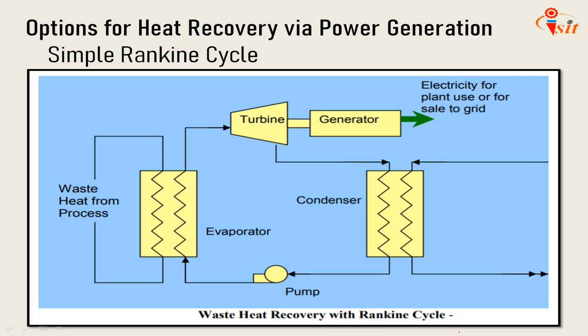At lower waste heat temperatures, steam cycles become less cost effective since low pressure steam will require bulkier equipment. Moreover, low temperature waste heat may not provide sufficient energy to superheat the steam, which is a requirement for preventing steam condensation and erosion of the turbine blades. Therefore, low temperature heat recovery applications are better suited for the organic Rankine cycle or Kalina cycle, which use fluids with lower boiling point temperatures compared to steam.